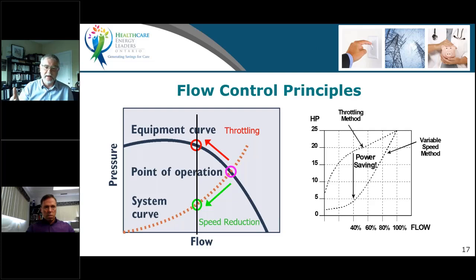So the opportunity then, as on the slide on the right, is that this converts to a situation where if we throttle a pump, we will reduce the power. There's no doubt, mildly reduce the power. But if we speed control a pump, we'll follow that system curve down, right? And we'll see a much more significant reduction in power overall.